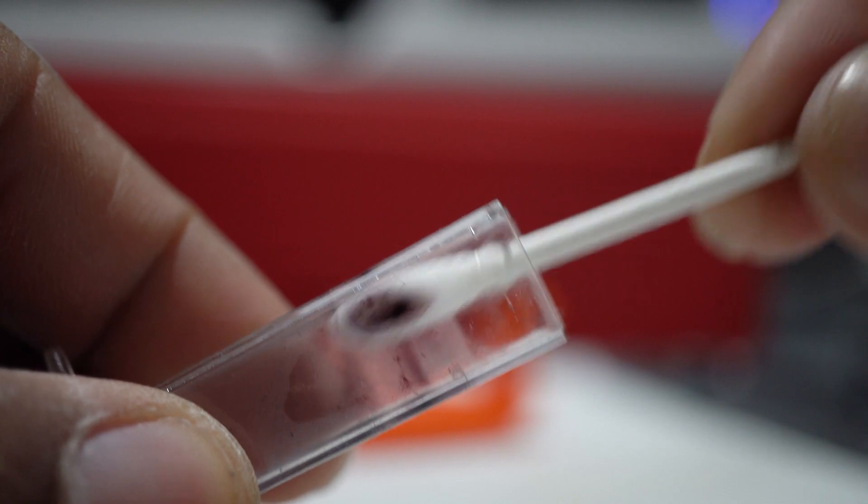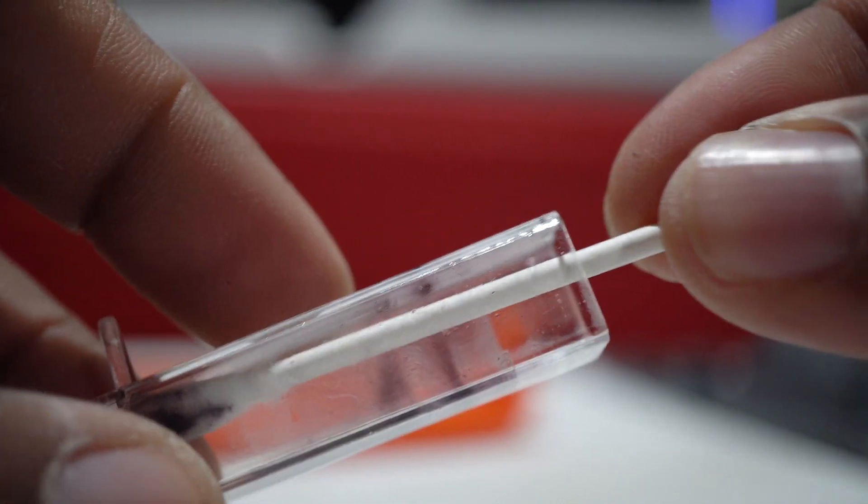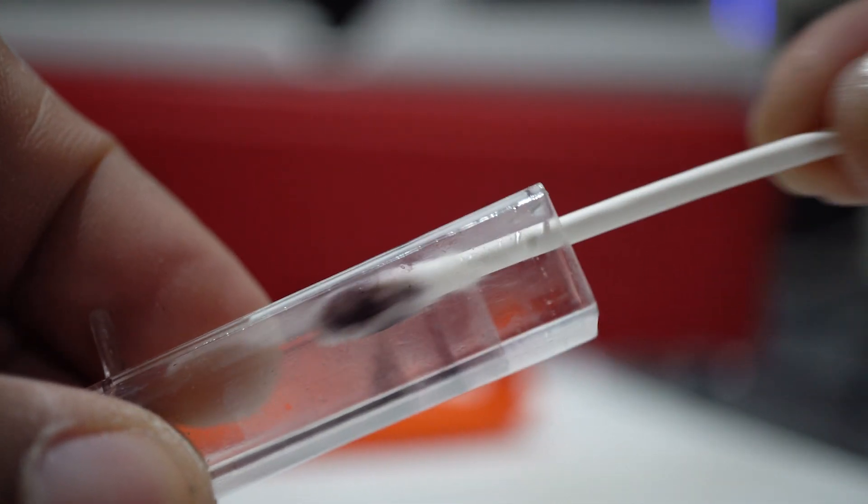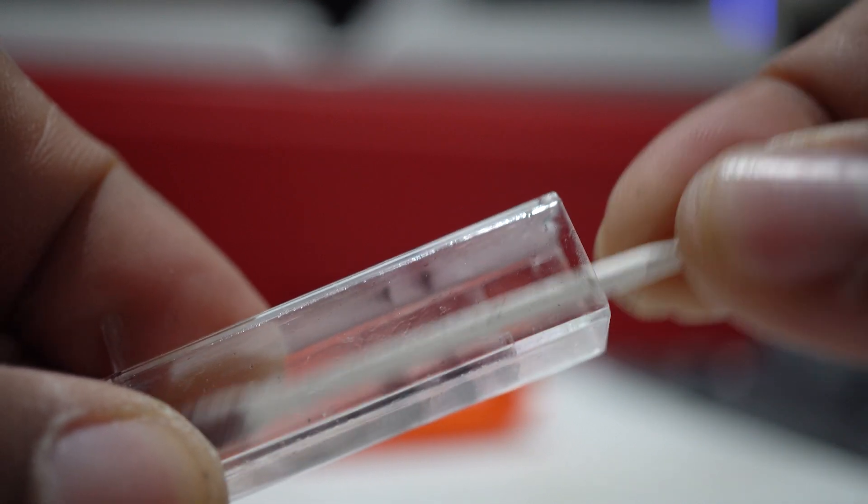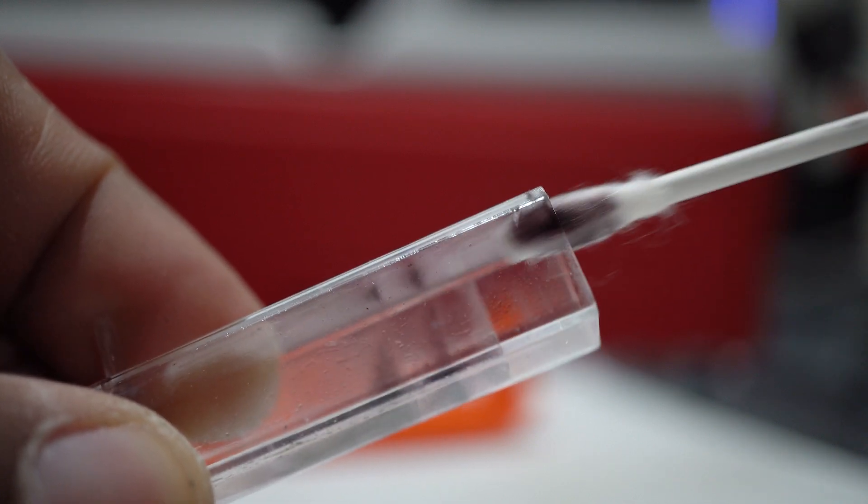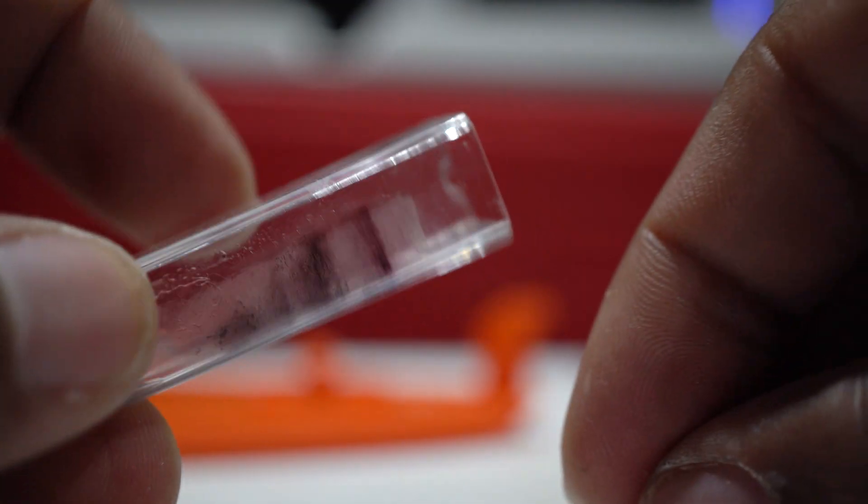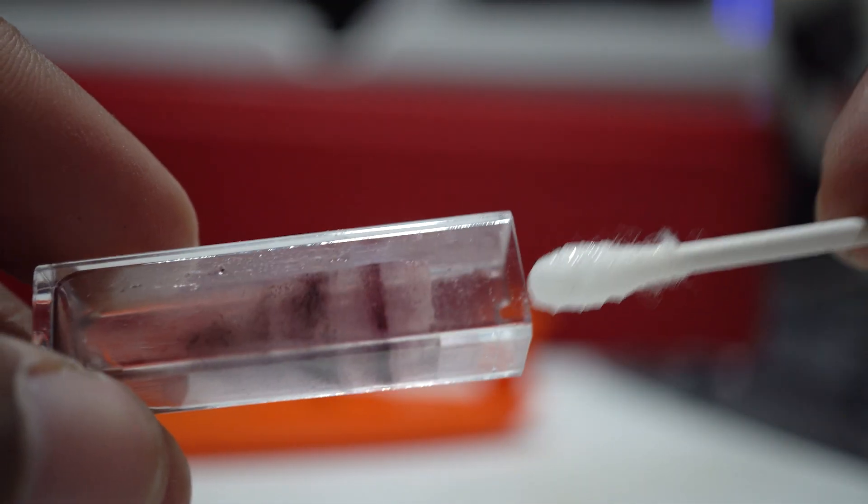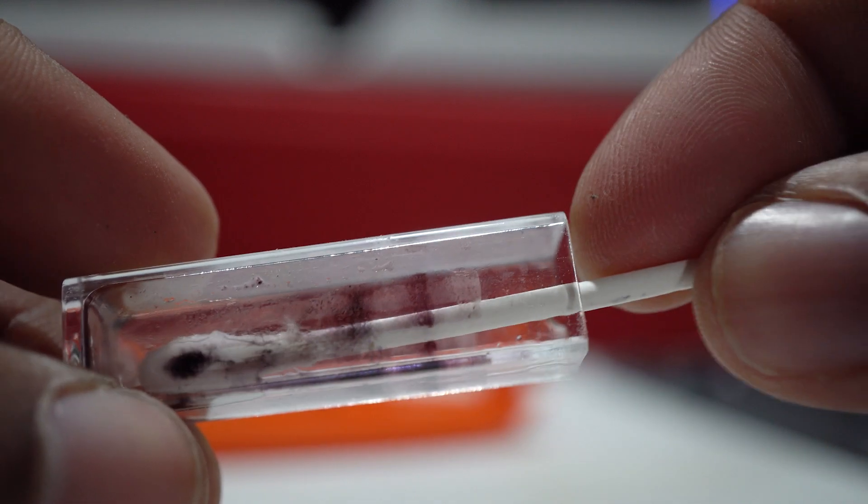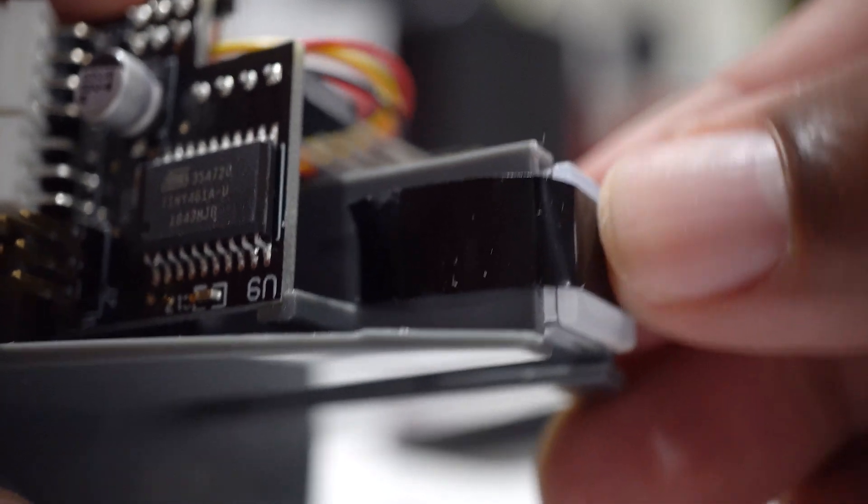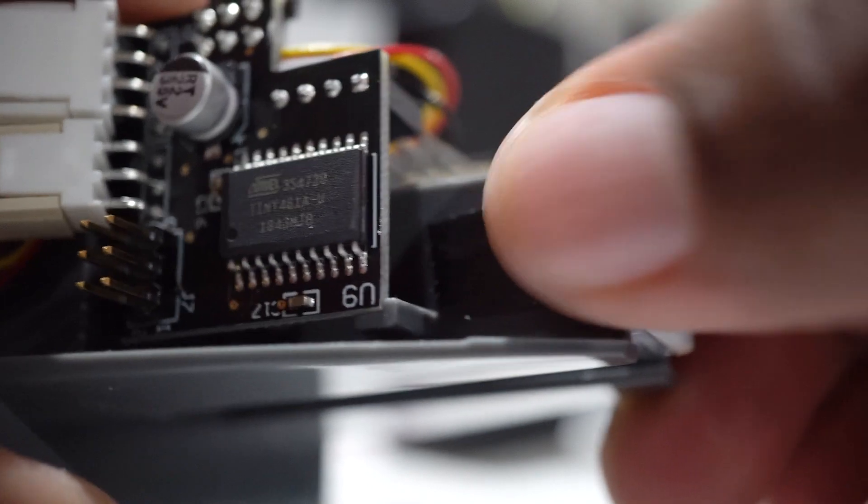After you finish cleaning out the chamber with the rubbing alcohol, you can go ahead and rinse the vial in RODI water and dry it thoroughly. You want to then reinstall the chamber, making sure that you clean it off very well with a lint-free cloth on both sides of the chamber that face the LEDs. You don't want to leave any fingerprints or any mess or anything like that on those sides. So with your chamber clean and ready to go, reinstall it into the housing. Reuse the same tape that it came with or replace that with some more electrical tape. Reconnect the clear tubing and put it back into the unit. It should clip right in.